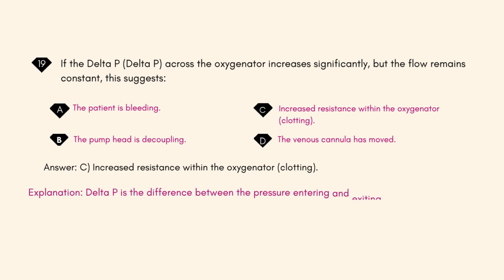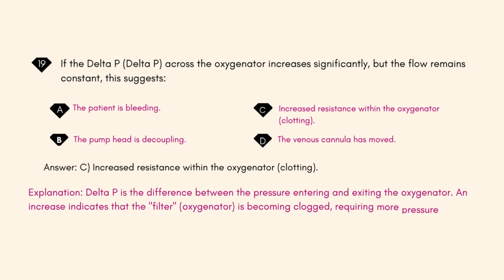Explanation: delta P is the difference between the pressure entering and exiting the oxygenator. An increase indicates that the filter, oxygenator, is becoming clogged, requiring more pressure to push blood through.